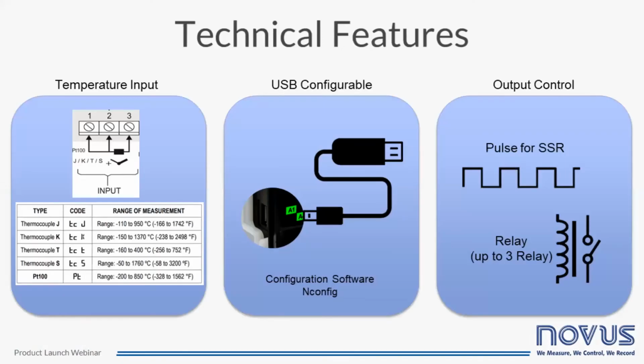Okay, let's go a little deeper into the technical features of the N1050. As it is a temperature controller, it accepts thermocouples and PT100. The accepted thermocouples are J, K, T, and S. Both input type and range are software configurable. For parameter settings of the N1050 via the USB port, the configuration software Nconfig can be used, which is free and available for download on the Novus website. Any common micro B type USB cable can be used for configuration, even those from a cellular charger.